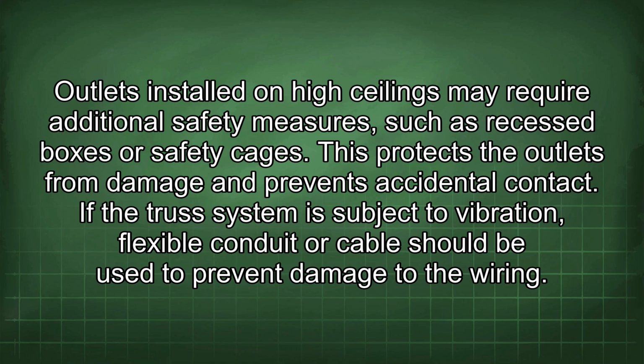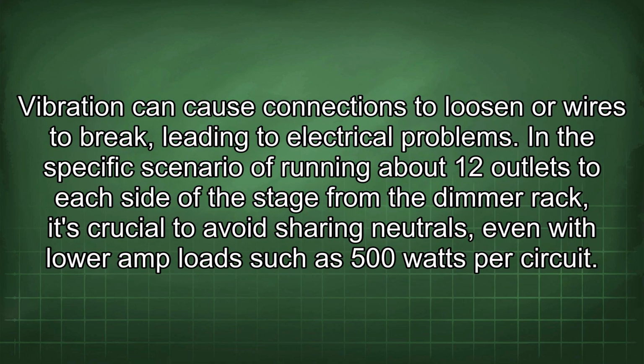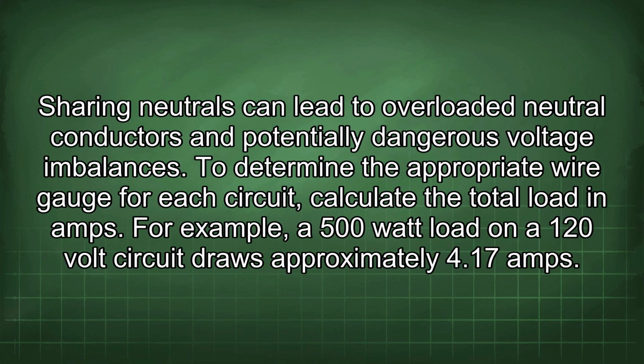If the truss system is subject to vibration, flexible conduit or cable should be used to prevent damage to the wiring. Vibration can cause connections to loosen or wires to break, leading to electrical problems. In the specific scenario of running about 12 outlets to each side of the stage from the dimmer rack, it's crucial to avoid sharing neutrals, even with lower amp loads such as 500 watts per circuit. Sharing neutrals can lead to overloaded neutral conductors and potentially dangerous voltage imbalances.